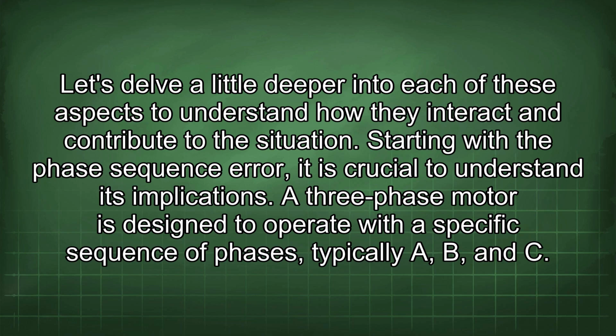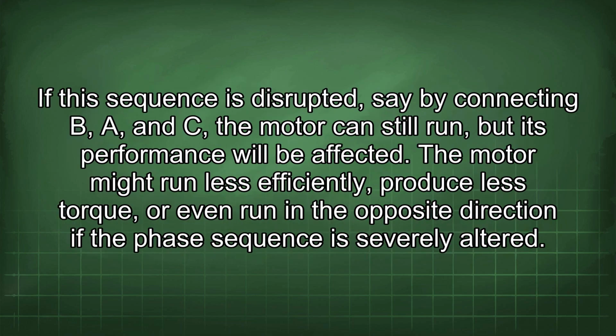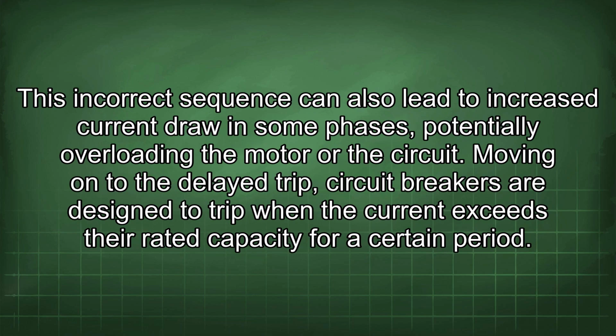Starting with the phase sequence error, it is crucial to understand its implications. A 3-phase motor is designed to operate with a specific sequence of phases, typically A, B, and C. If this sequence is disrupted, say by connecting B, A, and C, the motor can still run, but its performance will be affected. The motor might run less efficiently, produce less torque, or even run in the opposite direction if the phase sequence is severely altered. This incorrect sequence can also lead to increased current draw in some phases, potentially overloading the motor or the circuit.